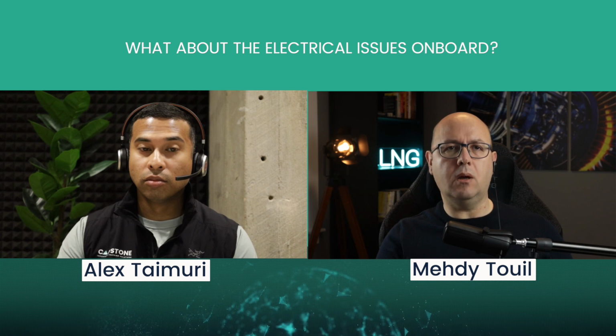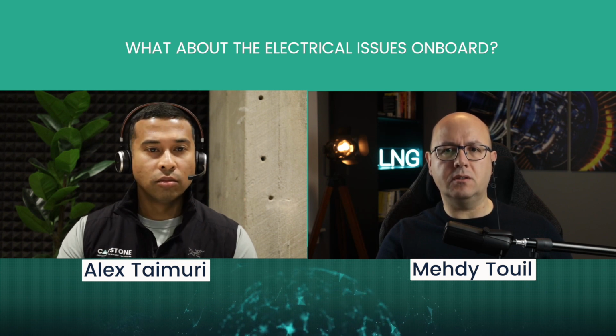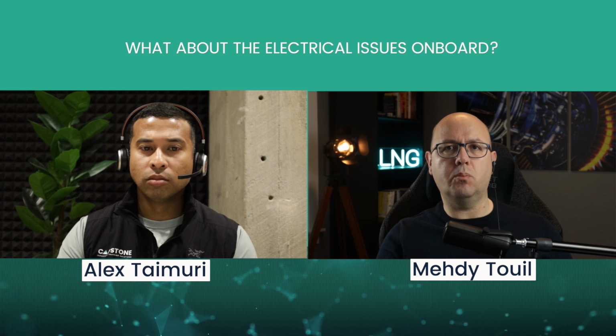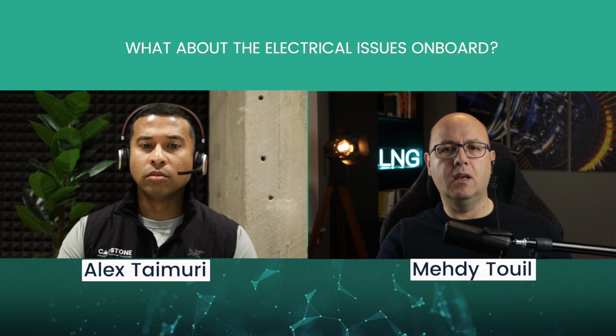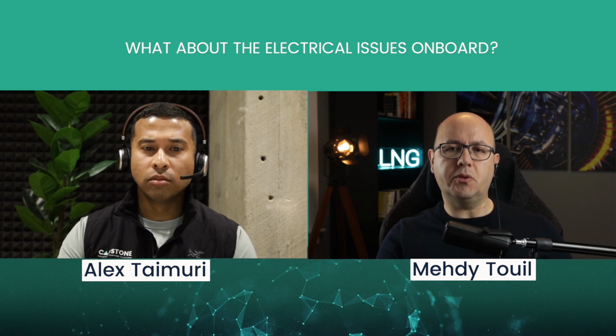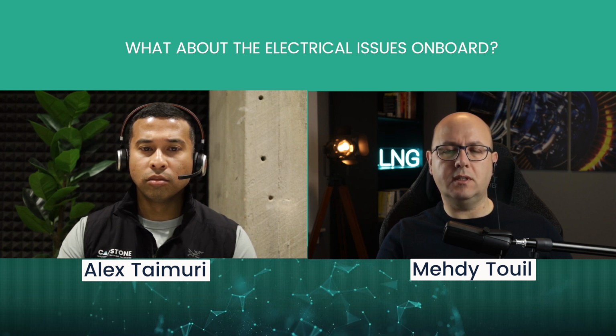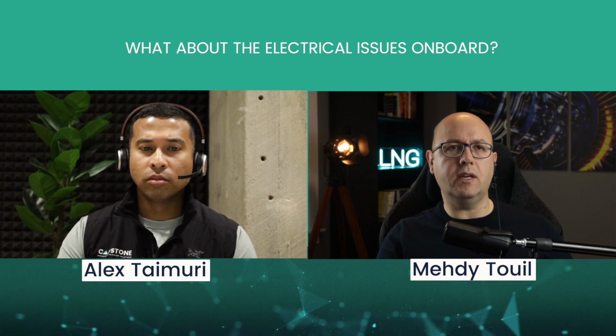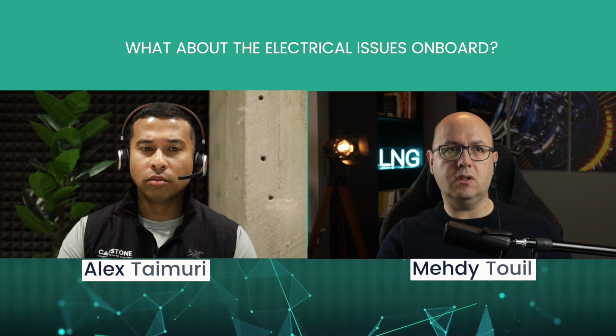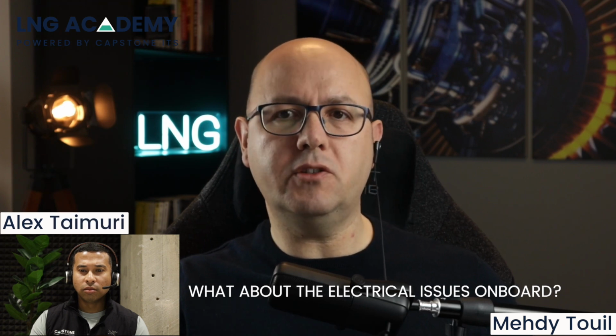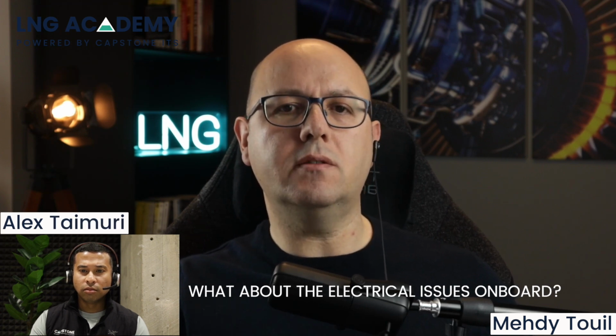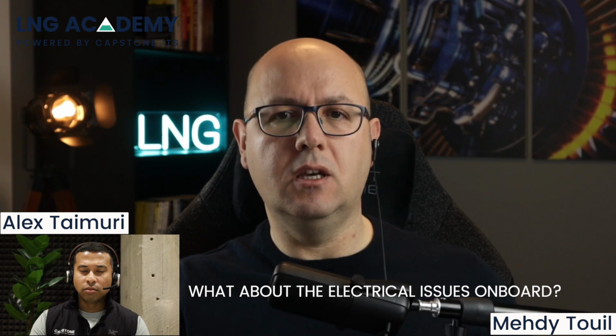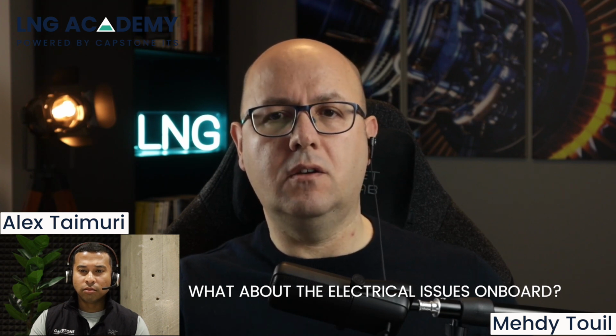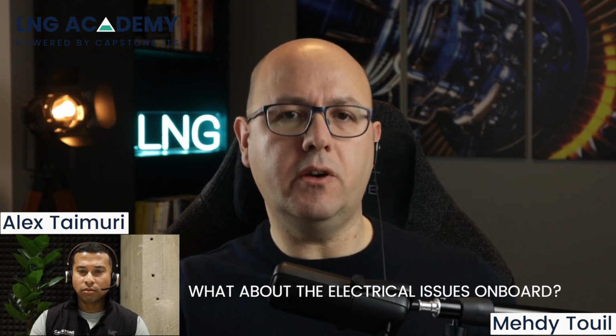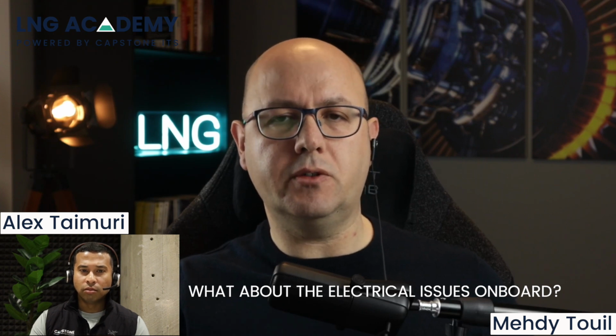So everything went down. Lighting, communication systems, HVAC, potable water, even sewage system. We have also the loss of heat tracing to prevent the cooling of the steel structures in the vicinity of the LNG tanks, which is a potential catastrophic scenario. So a main power plant trip, although a rare occurrence, can happen in any LNG facility, but a loss of plant air followed by backup emergency system failure is an extremely serious incident.